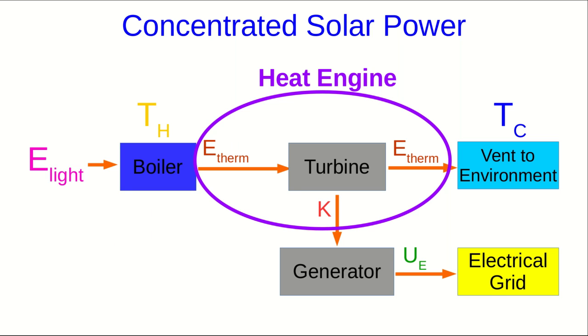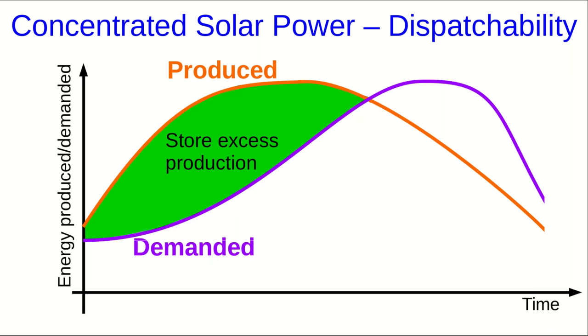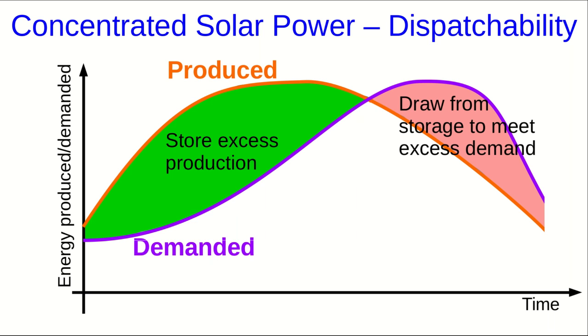The efficiency works out the same way it does for other thermal power plants, although the temperatures achieved are not always as high as in gas-fired plants. But concentrated solar power has a huge advantage: the heated fluid can be stored in insulated tanks, making it dispatchable. Anytime production is larger than demand, you can store the excess, and when demand is larger than production, you can draw from storage. Renewable sources that are dispatchable are relatively rare, which makes this a huge advantage.